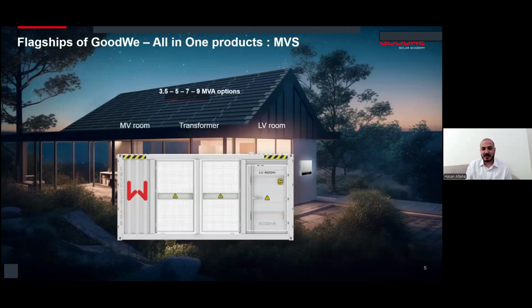And this is our MV station. Normally we use this MV station with our utility inverters. It has three parts, MV room and transformer and LV room. We have different sizes from 3.5 megavolt ampere up to 9 megavolt ampere.